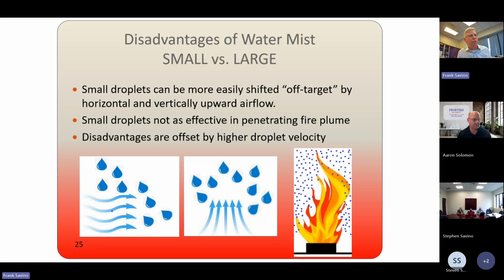I guess you'd follow the same rules as sprinklers, correct, Jeff? Yeah. We've done data centers with regular pre-action sprinkler that are set up like he's describing, where because of the containment you end up needing to protect the above ceiling because it's open. So yeah, if you were using water mist in the room, I would use it above the ceiling there too. And so you end up having to put it over the entire ceiling, just like you would have to put it below the entire ceiling. Correct, it would follow the same layout. It would be very similar to the pre-action sprinkler, just with water mist instead. You would have to do the whole above ceiling there. It would be like a 3 or 4 foot cavity, and so mist would operate just as well in that environment as it does in the room itself. Yes, I believe it would. Okay.